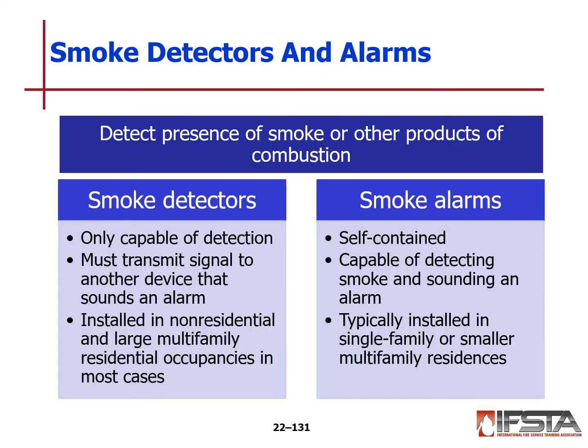Smoke detectors and alarms basically will detect the presence of smoke or other products of combustion. With your smoke detectors, they're only capable of detecting; they must transmit the signal to another device that then sounds the alarm. And this is installed in non-residential and large multifamily residential occupancies in most cases. Smoke detectors, again, they detect, they send that to the panel. The panel will then set the alarm off.